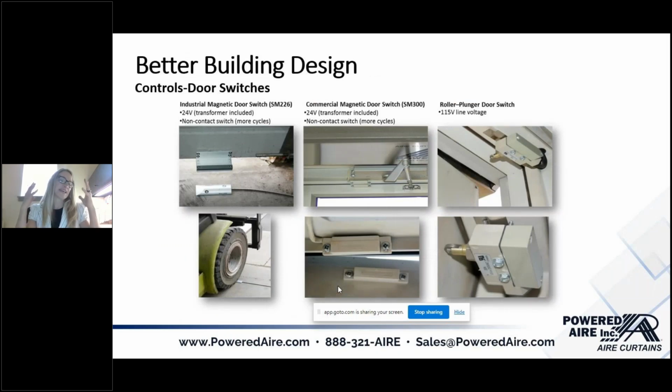Sticking with better building design, talking about controls, 99% of the air curtains that we ship leave our plant with some kind of door switch. Sadly, what has become standard in the industry is this picture on the right, which is a roller plunger. It is big, it is bulky. If something's going to break, it's going to be this roller arm. I try to encourage engineers and users, please do not specify this, do not use this. There's so many better options.